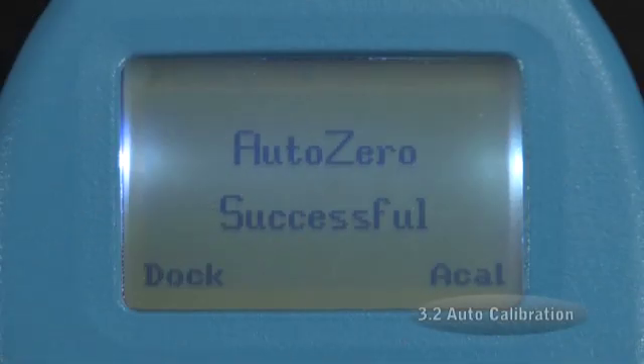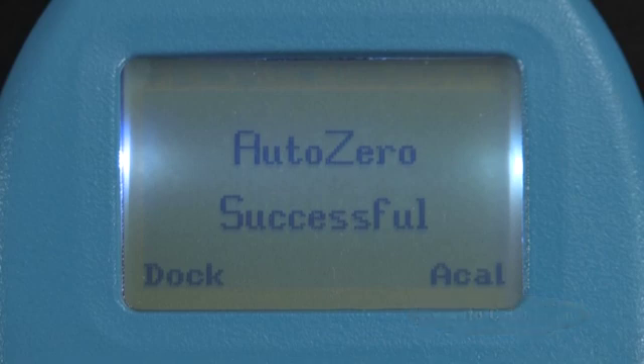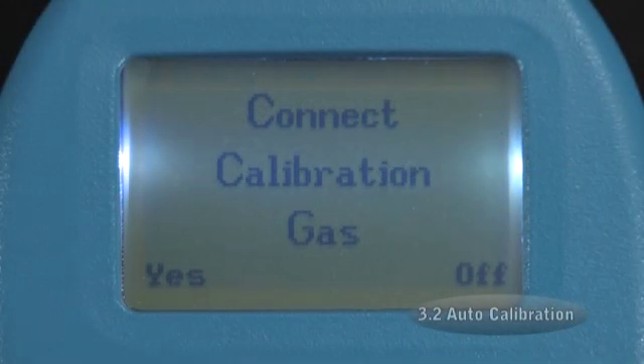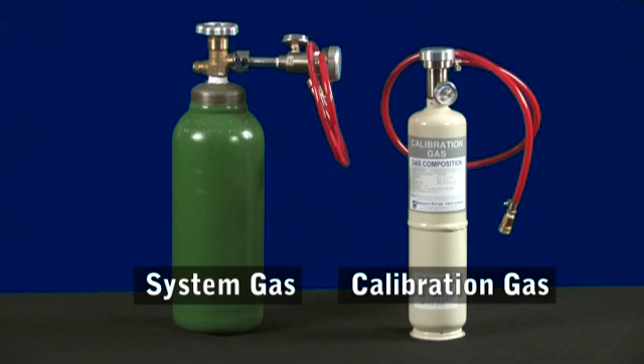First, we'll calibrate the Explorer without using a docking station. Once the Auto Zero Successful screen appears, press the button on the right under ACAL. After pressing the ACAL button, you will be prompted to Connect Calibration Gas. The Explorer should be calibrated using 2 gases: Bascom-Turner's calibration gas, which consists of 2.5% methane, 100 ppm CO with a balance of air, and with 100% methane or system gas. Each gas is introduced separately. Preferably, 100% methane or system gas is used first.